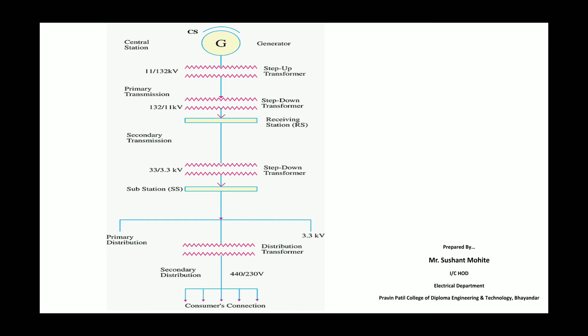In this diagram there are 5 important parts: the generating station, then primary transmission, then secondary transmission, then primary distribution, and the last is the secondary distribution. The first, generating station: the place where electrical power is produced by parallel connected 3-phase alternators or generators is called a generating station. The ordinary generating voltage may be 3.3 kV, 6.6 kV, 11 kV. But economically, it is good to step up the produced voltage from 3.3 kV, 6.6 kV, 11 kV to 110 kV, 132 kV, 220 kV, 400 kV by a step up transformer or power transformer.